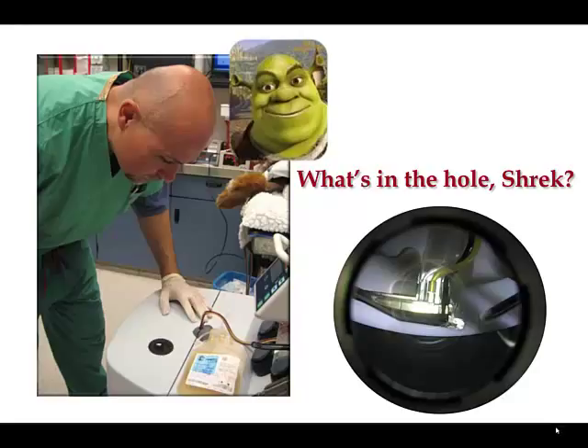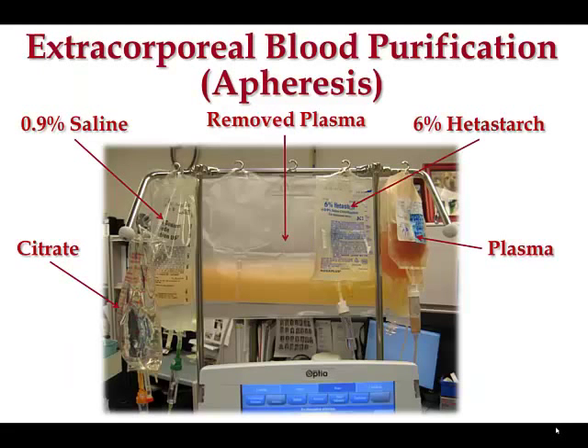Here's a real-life chamber sitting in the centrifuge — the centrifuge goes around, and you can see the red blood cell layer, the white cell layer, and plasma sitting on top. The contaminated dirty plasma gets collected in a removal bag. The extracorporeal circuit is anticoagulated typically with citrate to prevent clotting, so we have a citrate bag, saline to prime the machine and apply volume, a bag for all the bad stuff, and bags for the replacement solution — which could be plasma, colloid, or albumin.